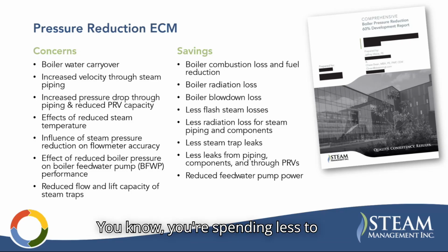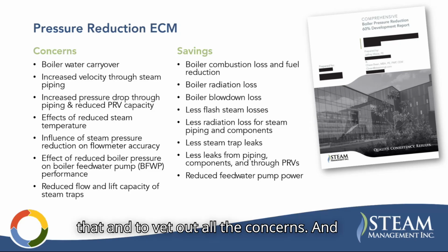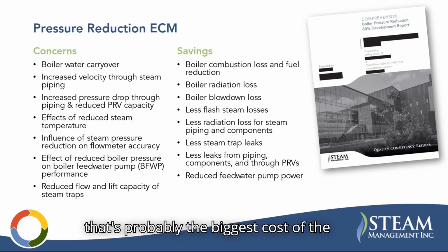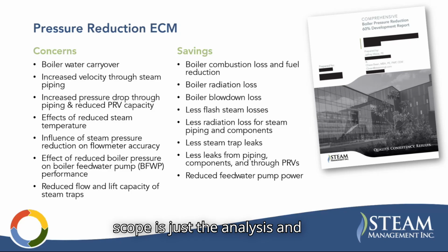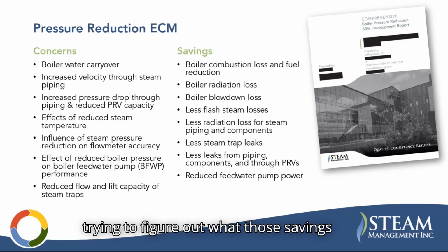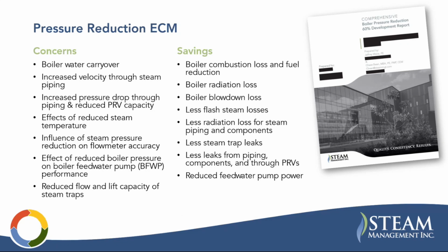You're spending less to generate the steam if you're reducing the pressure at the boiler. So there's a lot of savings to be had, and it takes an engineering analysis to quantify all that and to vet out all the concerns. That's probably the biggest cost of the scope, just the analysis and trying to figure out what those savings are, and whether all of those concerns are vetted out so that they're not going to be an issue.